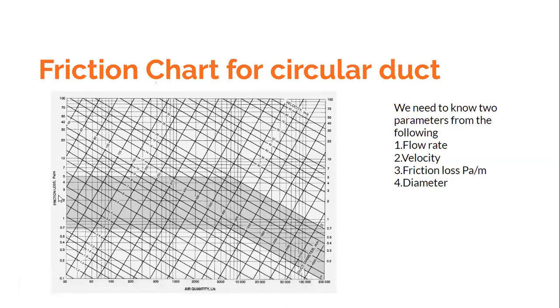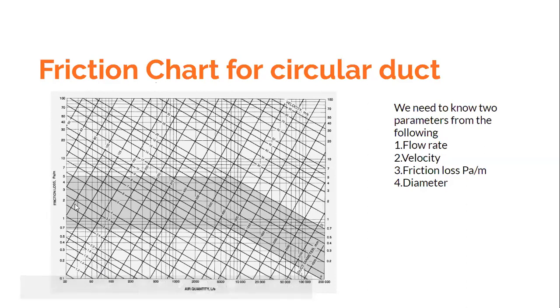I have shown a friction chart here. On one axis there is friction loss, or friction rate — expressed in units of pressure per unit length of duct, such as Pascals per meter, or it could be expressed as mm of water per meter length of duct. In this chart in front of you, the friction rate in Pascals per meter is plotted on the y-axis.